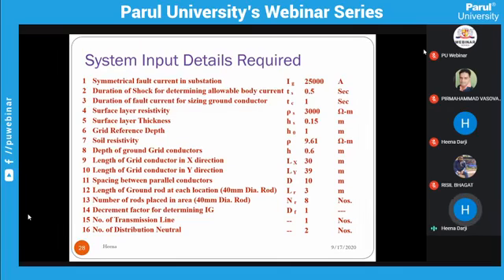Your soil resistivity depends on the place, we already learned about this. Here the soil resistivity is 9.61. We are using the earth resistance mapping. Now, your grid conductor, means your mat, how deep it is in the ground. This depth is 600 mm, and if your soil resistivity is very high, you have to go down to 1 meter. So it depends on your resistivity.